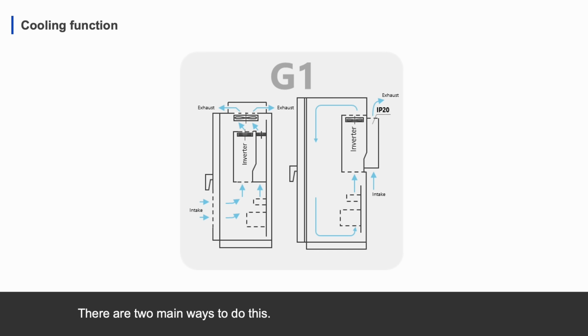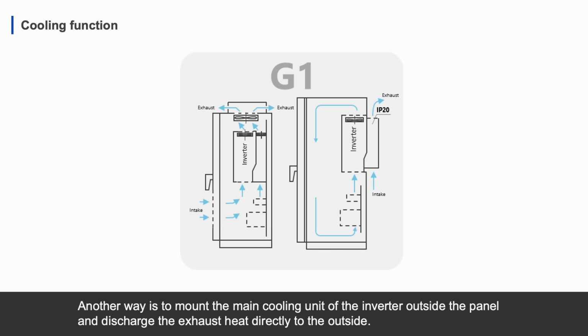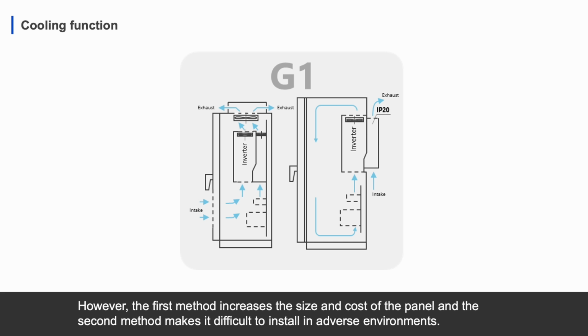There are two main ways to do this. One way is to install fans and heat exchangers in the panel. Another way is to mount the main cooling unit of the inverter outside the panel and discharge the exhaust heat directly to the outside. However, the first method increases the size and cost of the panel, and the second method makes it difficult to install in adverse environments.